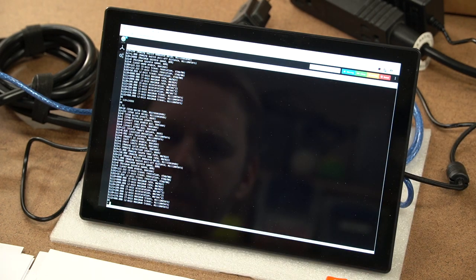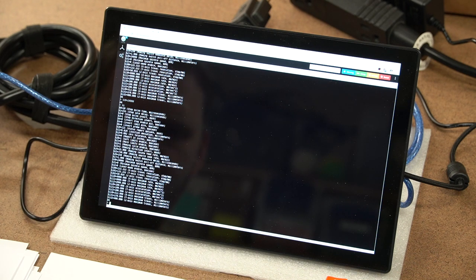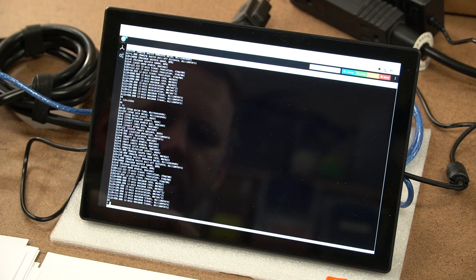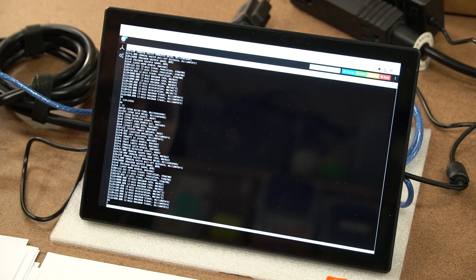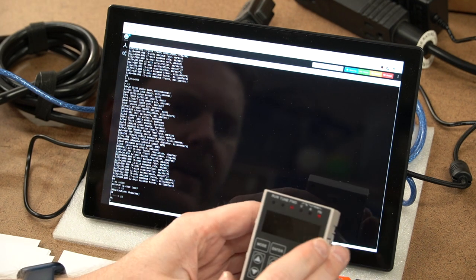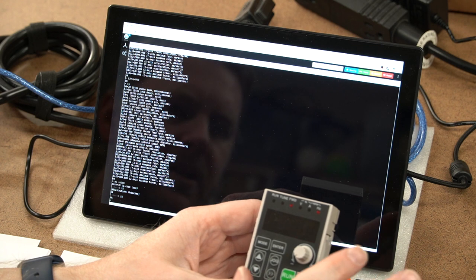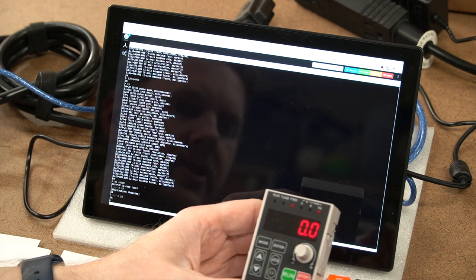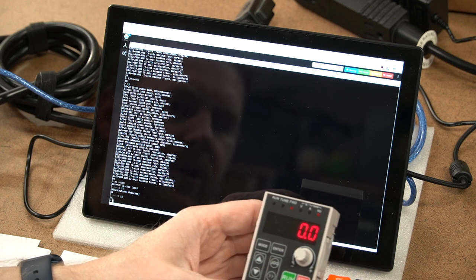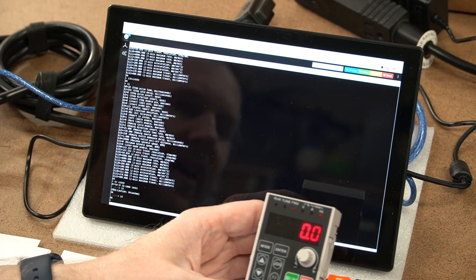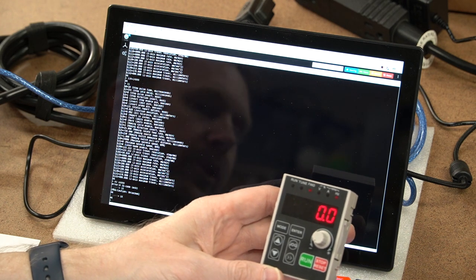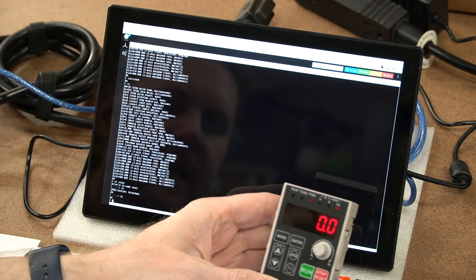We've got our settings configured and now we can go ahead and play with our settings. So if we switch to page 24 of the manual, down towards the bottom, I've got a section called automatic control testing. This allows you to configure and control your machine. All right, here we are with our keypad. It's blinking, which means it's not actually running, which means I can send it some command PWM signals. It will change the frequency, show us that frequency, but it won't actually spin the motor. It allows us to validate, make sure our commands and our controller knows how to properly talk to it. We can validate our voltages and that sort of thing through this mechanism.